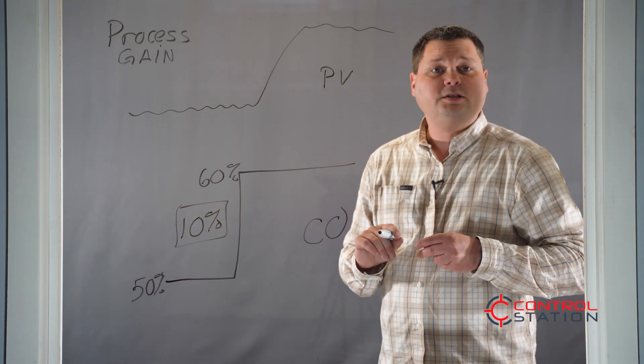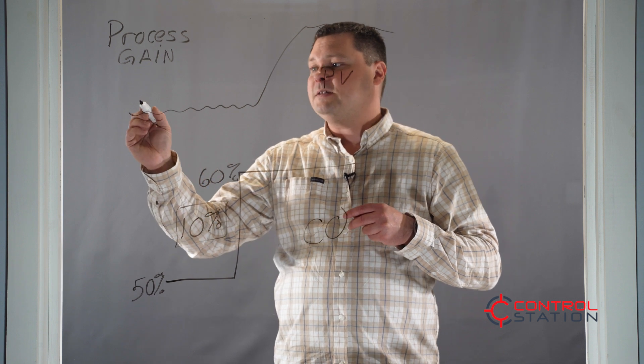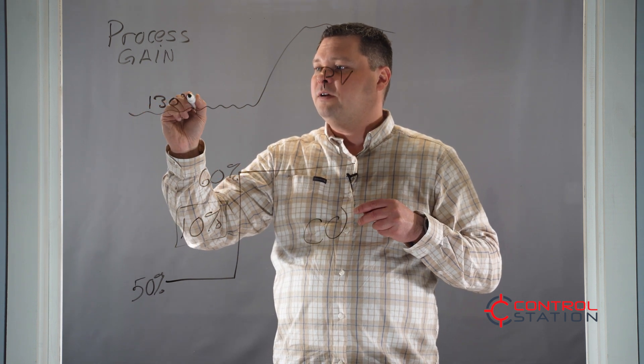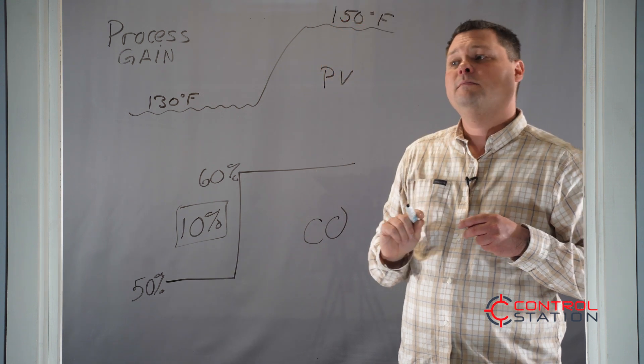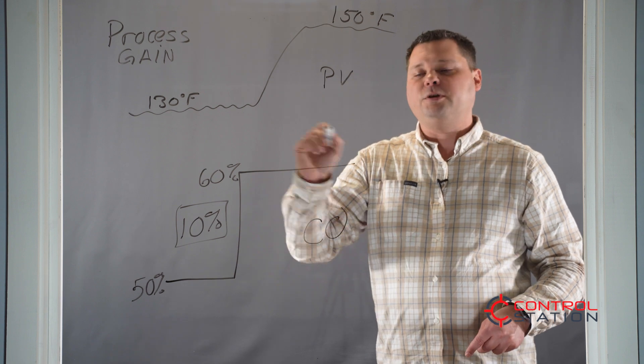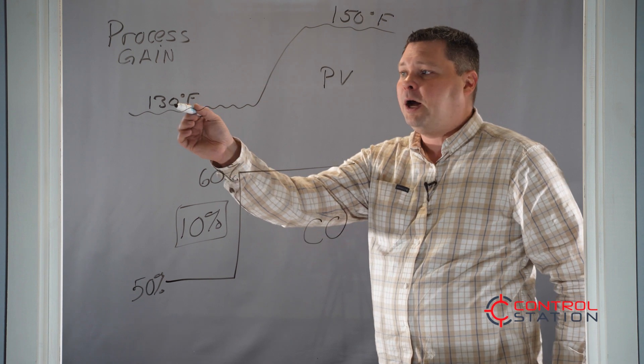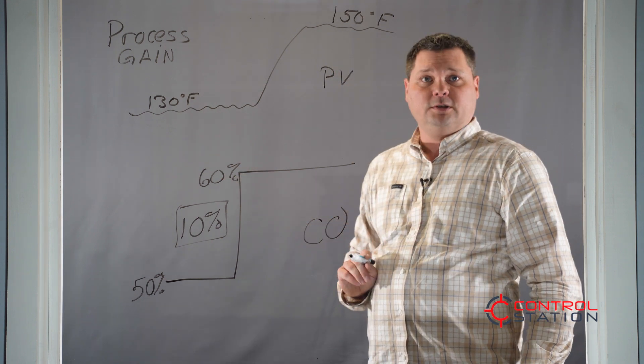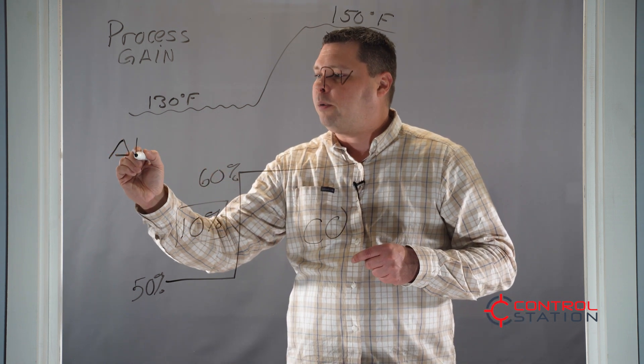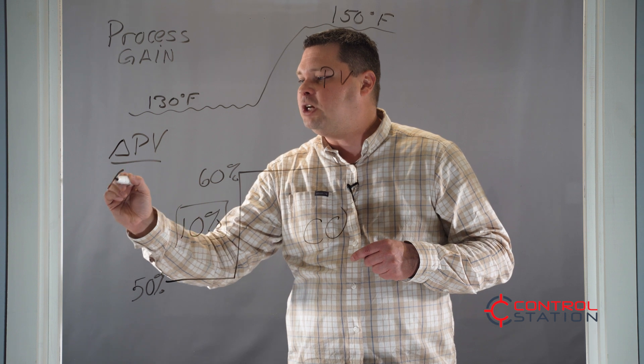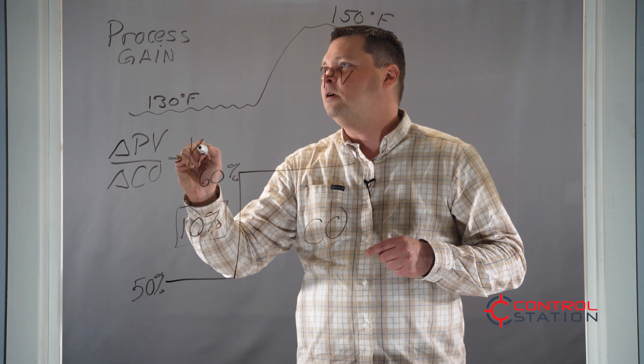How far did the process variable move? For that we're going to need to measure the process variable. In this case let's say we went from 130 degrees Fahrenheit to 150 degrees Fahrenheit. So we moved the controller output 10 percent, opened the control valve 10 percent, and our temperature went from 130 to 150 degrees. Our process gain Kp is how far the process variable moved divided by the change in our controller output.